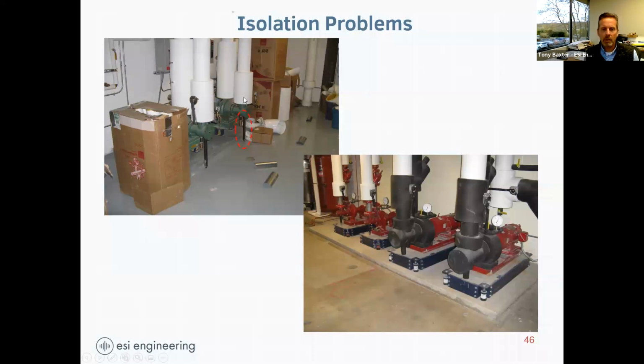But then they supported the suction side piping with a post here that goes down to the ground. So the vibration from this pump is coming this way and going into the floor. The way it should be done is like this - that post, that support, should be on the housekeeping pad. I mean, it's just kind of common sense, right? But it's surprising how often we see it done like this.